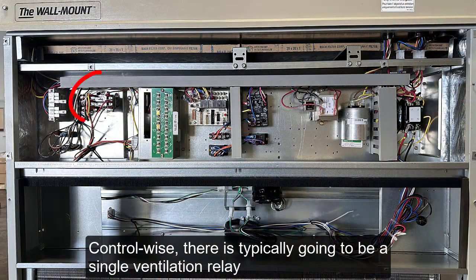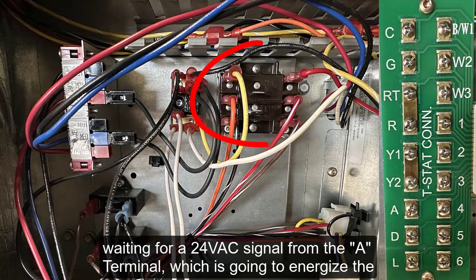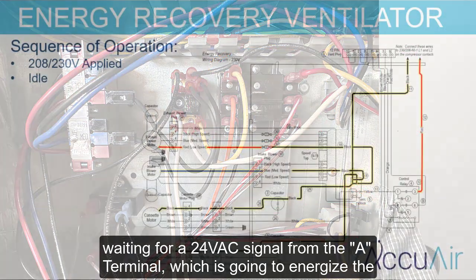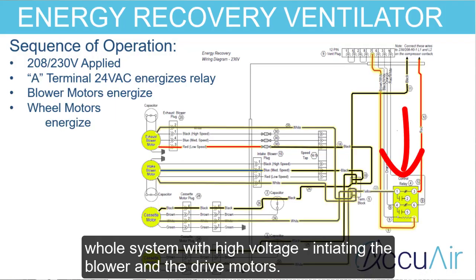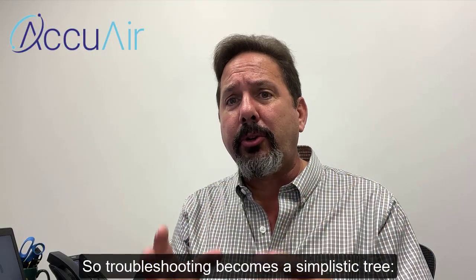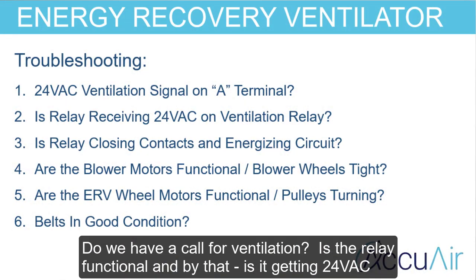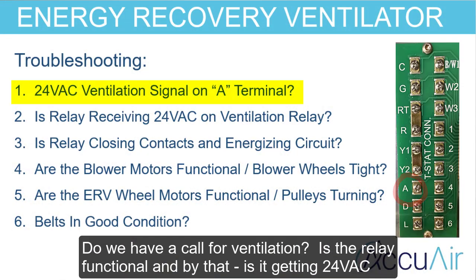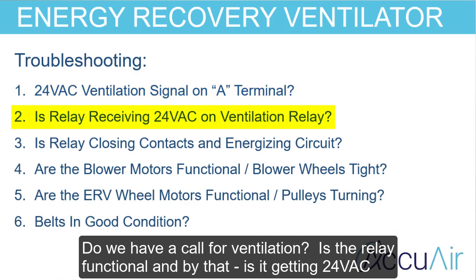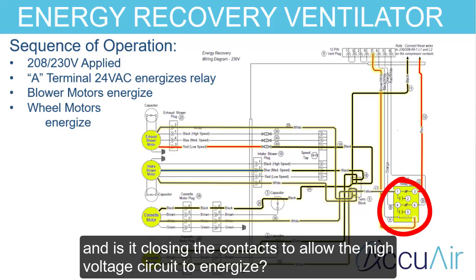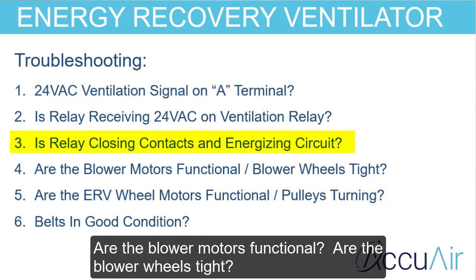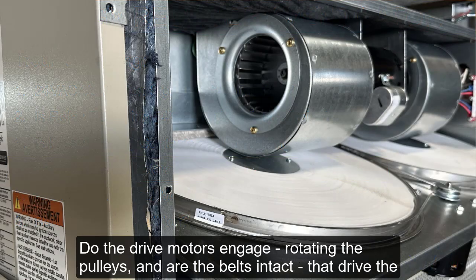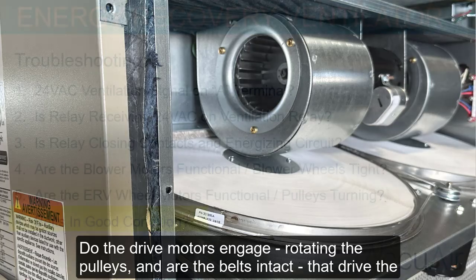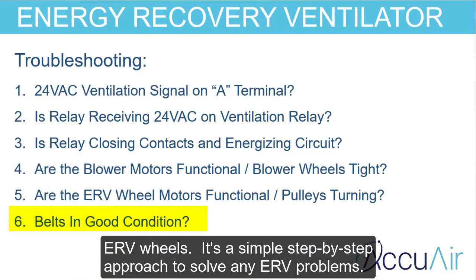Control-wise, there's typically going to be a single ventilation relay waiting for a 24-volt signal from the A terminal, which is going to energize the whole system with high voltage, initiating the blower and the drive motors. So troubleshooting becomes a simplistic tree. Do we have a call for ventilation? Is the relay functional? And by that, is it getting 24 volts and is it closing the contacts to allow the high voltage circuit to energize? Are the blower motors functional? Are the blower wheels tight? Do the drive motors engage, rotating the pulleys, and are the belts intact that drive the ERV wheels? It's a simple step-by-step approach to solve any ERV problem.